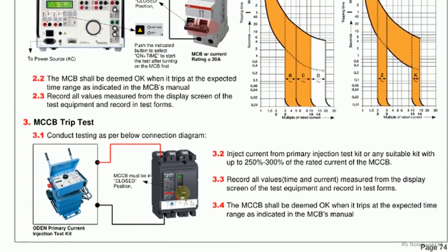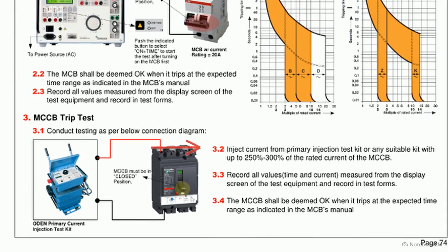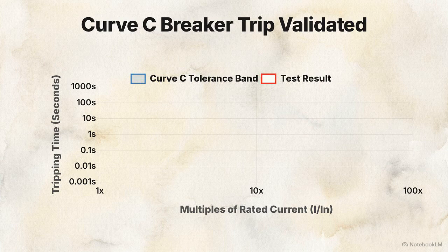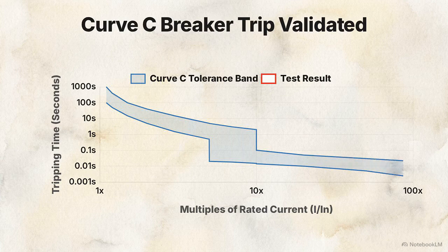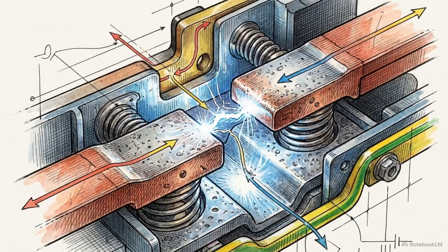For larger MCCBs, primary current injection pushes up to 300% of rated current through the main contacts to force an operation. This graph maps the exact trip time and current response of the breaker against standard tripping characteristics like B, C, D, K, or Z curves. The recorded data point must fall within the specific shaded tolerance band of its assigned curve. A breaker's physical form is irrelevant until its tripping curve is empirically proven to interrupt fault currents within precise milliseconds.